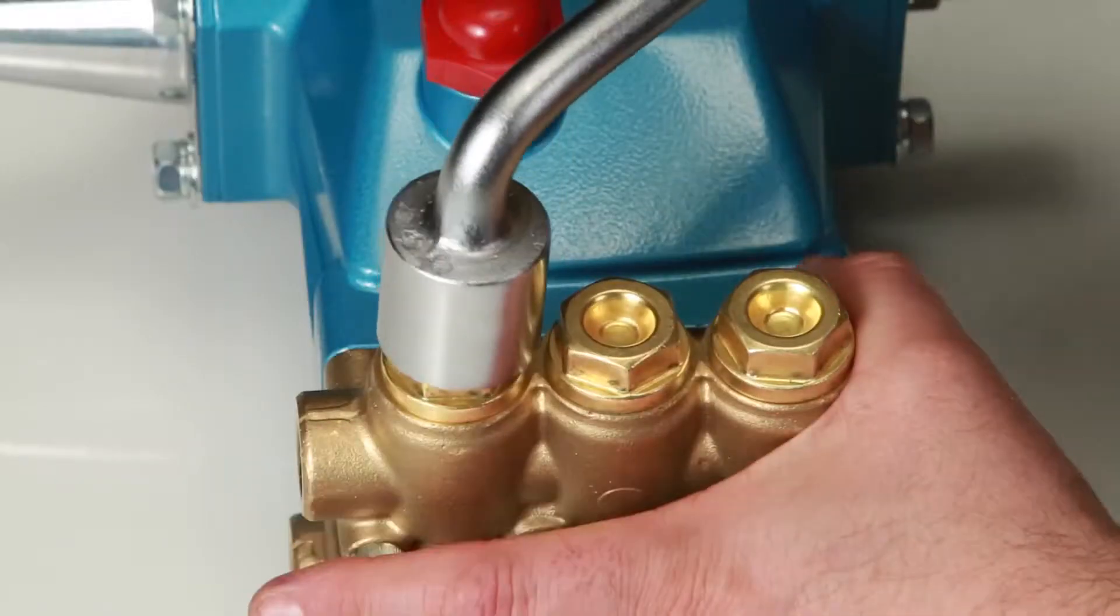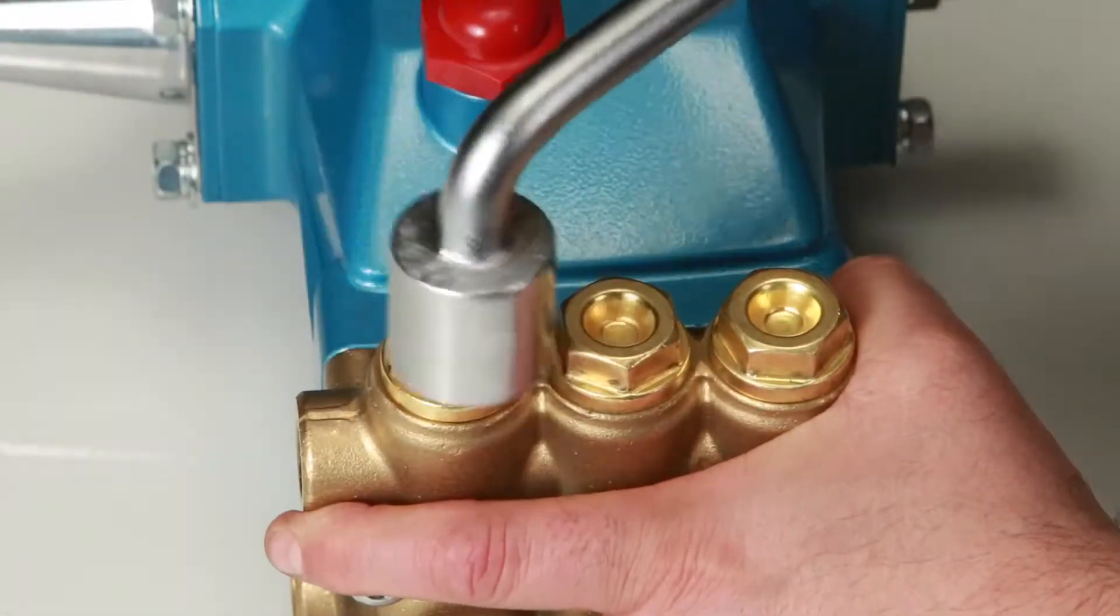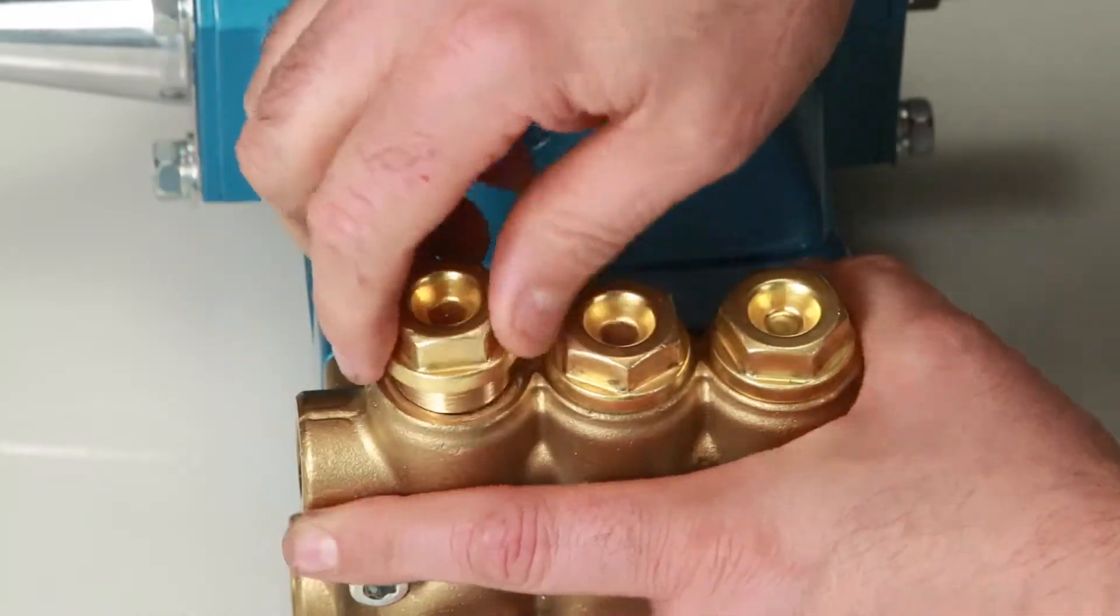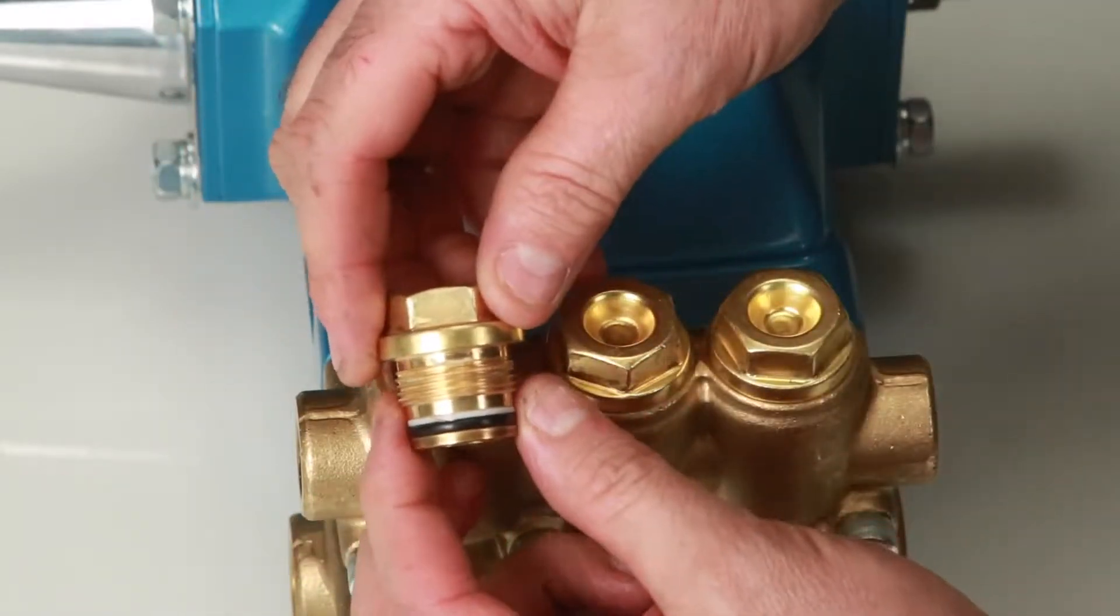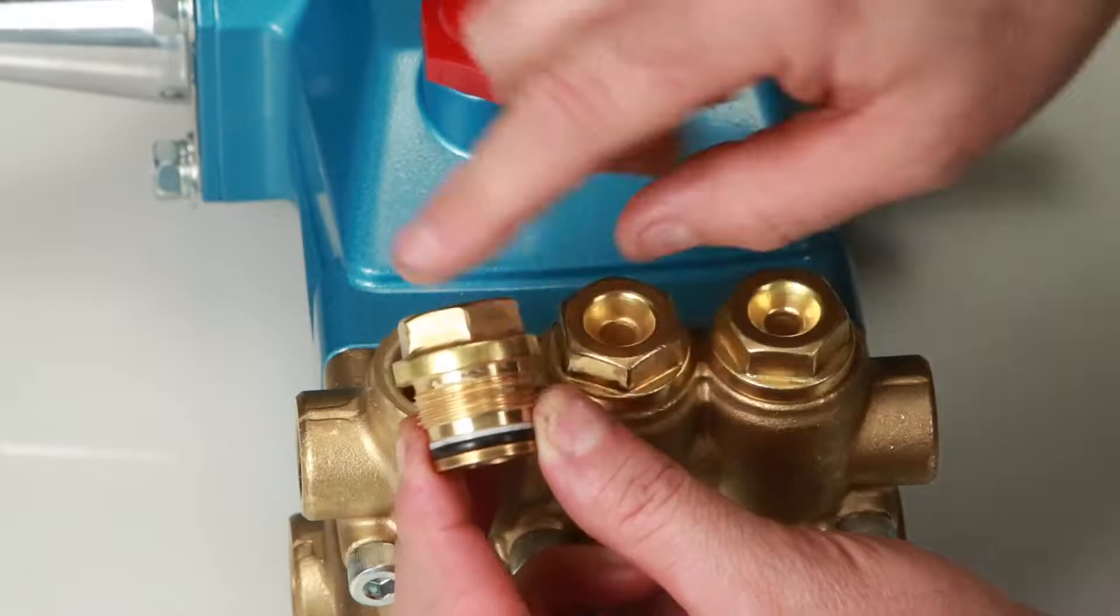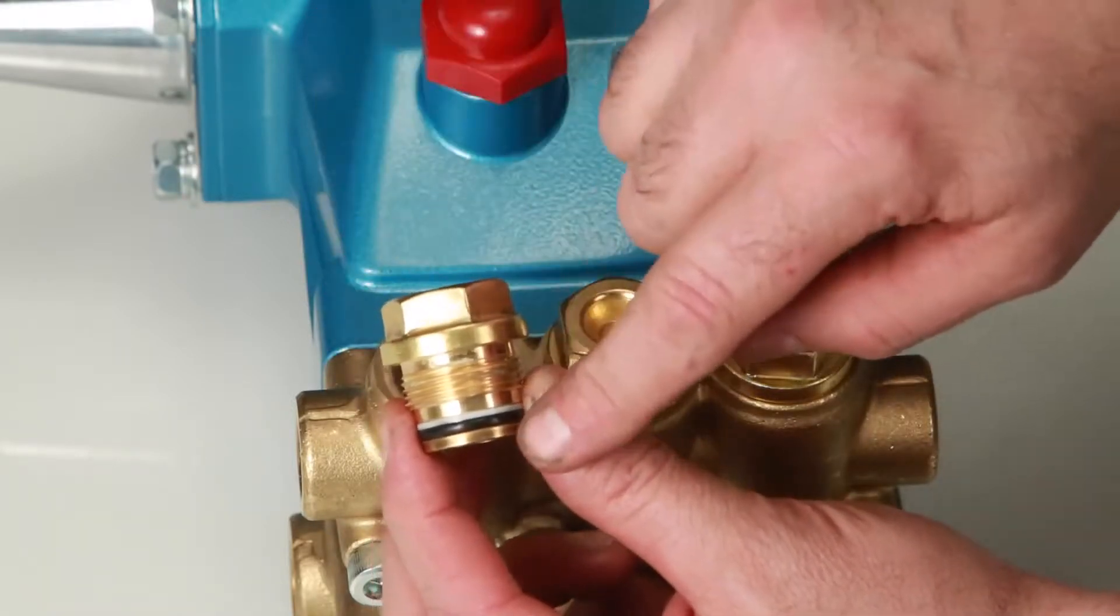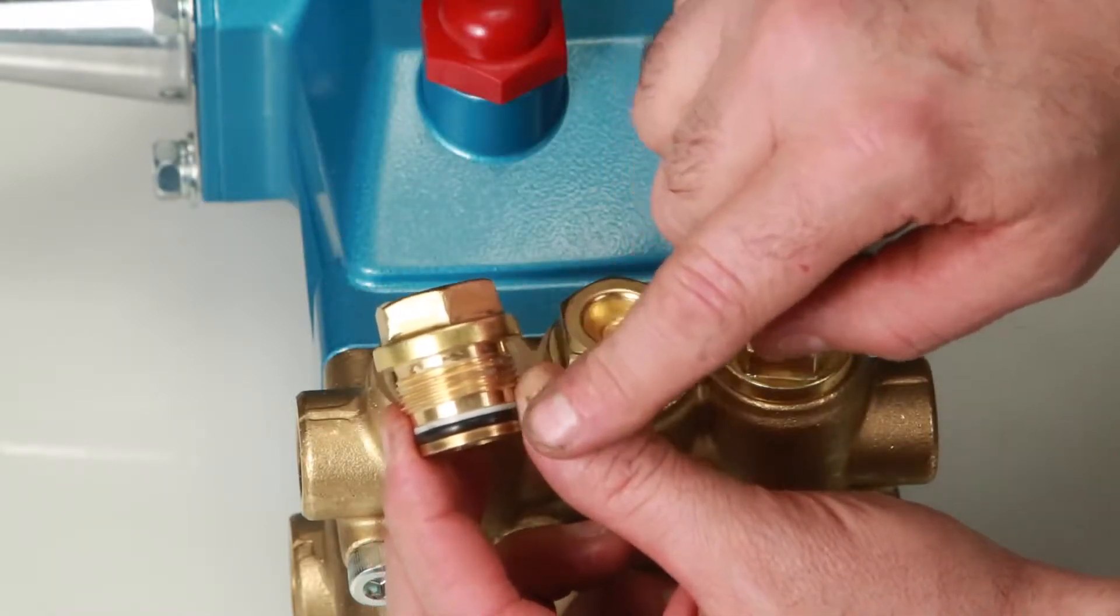To begin servicing the valves, remove the valve plugs using a 24mm hex wrench. After removing the valve plugs, be sure to inspect the O-ring and backup ring for any damage, or replace with new parts included in a valve kit.